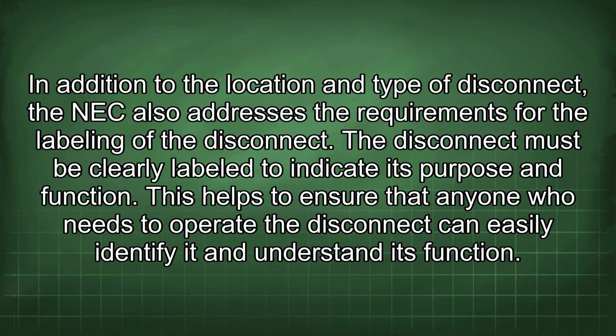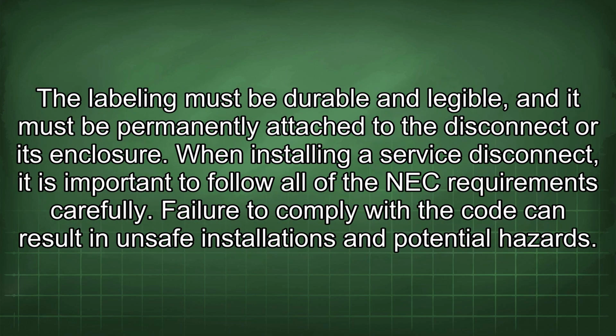In addition to the location and type of disconnect, the NEC also addresses the requirements for the labeling of the disconnect. The disconnect must be clearly labeled to indicate its purpose and function. This helps to ensure that anyone who needs to operate the disconnect can easily identify it and understand its function. The labeling must be durable and legible, and it must be permanently attached to the disconnect or its enclosure.